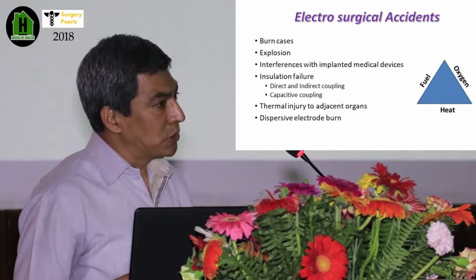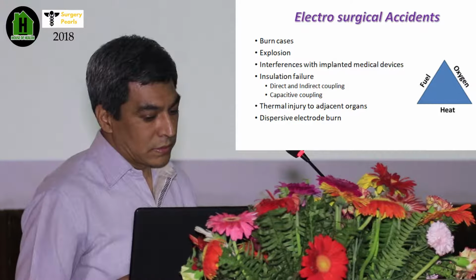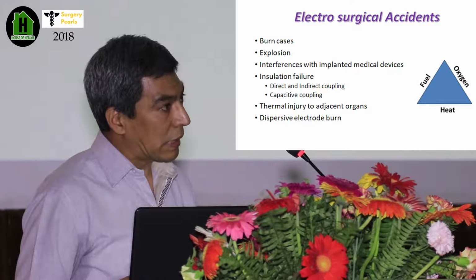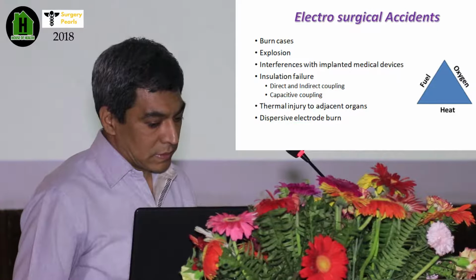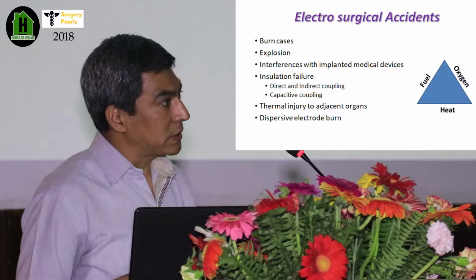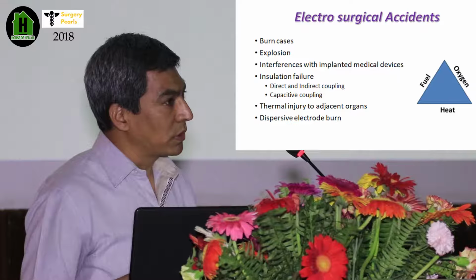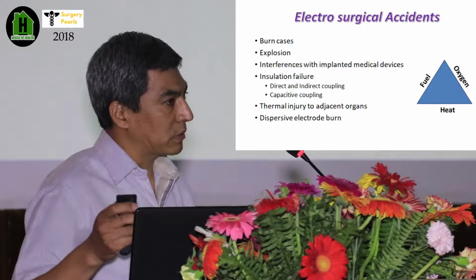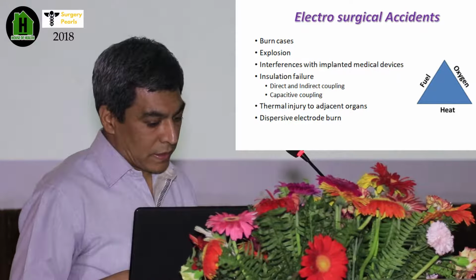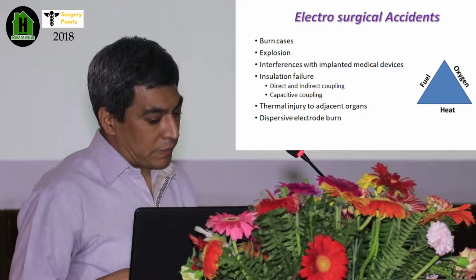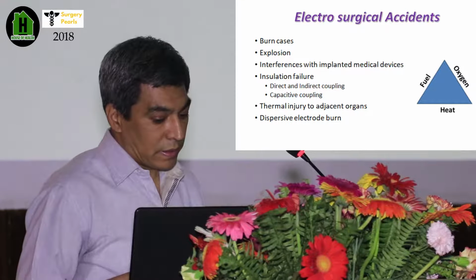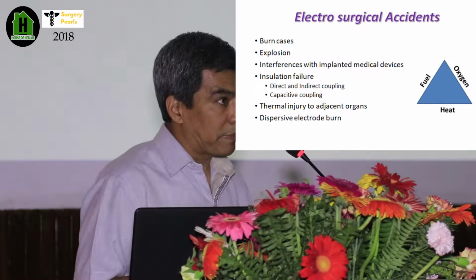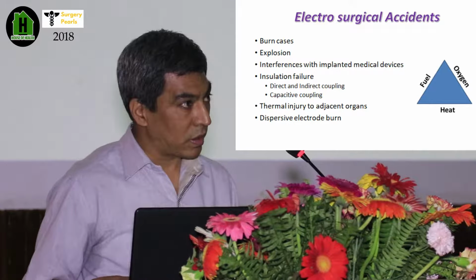If there is failure in the insulation, it might give a coupling effect or capacitive effect. It might cause thermal injury to the adjacent structures or organs. We won't know how much heat has been transmitted while using this. And it might cause dispersive electrode burns because of passive electrodes that are not properly placed.